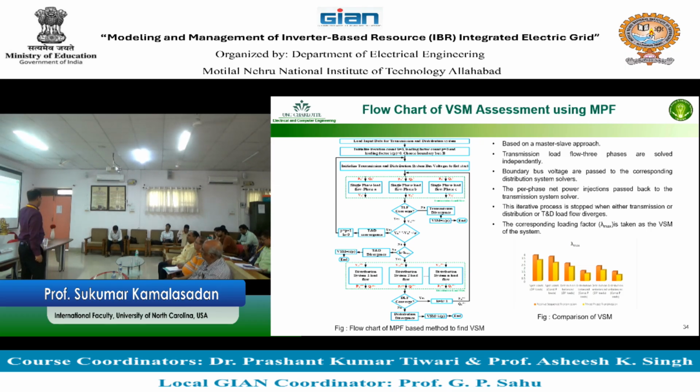This actually happened in doing the interconnection for the photovoltaics. I think we will be doing an interconnection study here too. When you are connecting a PV farm to an electric grid, before the connection is done, you have to do what we call interconnection studies.